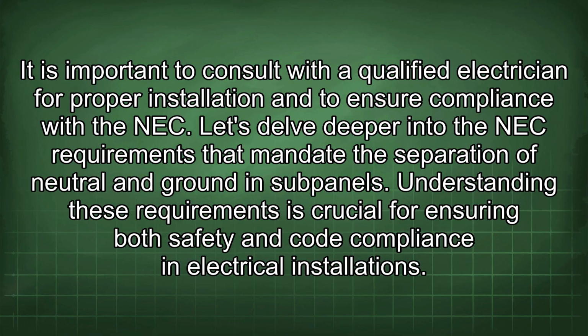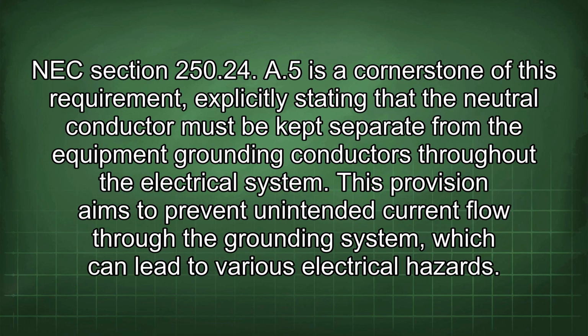Let's delve deeper into the NEC requirements that mandate the separation of neutral and ground in subpanels. Understanding these requirements is crucial for ensuring both safety and code compliance in electrical installation. NEC section 250.24(A)(5) is a cornerstone of this requirement, explicitly stating that the neutral conductor must be kept separate from the equipment grounding conductors throughout the electrical system. This provision aims to prevent unintended current flow through the grounding system, which can lead to various electrical hazards.